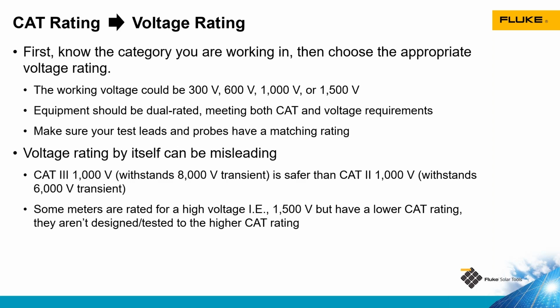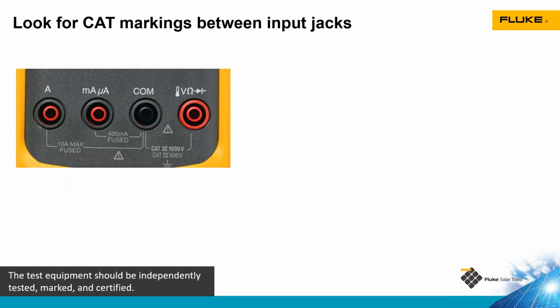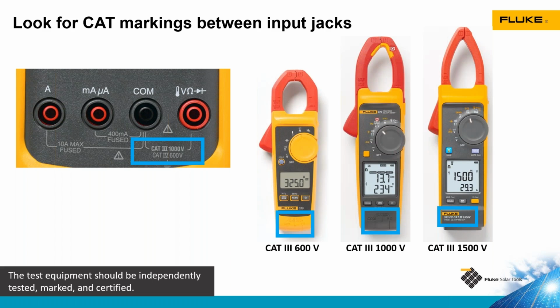All of the Fluke tools, if they are designed to measure a certain voltage, they are tested to that voltage level. You can find the category ratings right on the test tools. In this example, we have a multimeter with a Category 3 1,000 volt rated, Category 2 600 volt rated. Here's an example of a couple of our clamp meters. The 325 clamp meter on the left is Category 3 600 volt rated. The 378 in the middle is Category 3 1,000 volt rated, and the 393 is Category 3 1,500 volt rated.